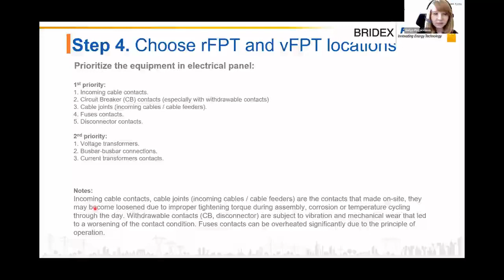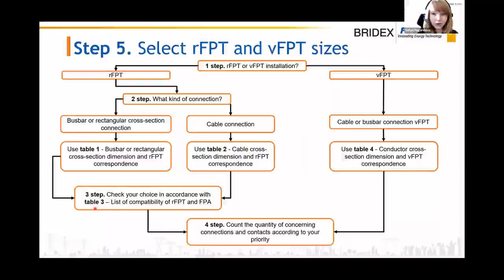This is a cross-section of middle voltage switchgear. So we install gas stickers on busbar connections, especially those made on site, on moving contacts of withdrawable contacts of circuit breakers, on contacts of current transformer, on incoming cable contacts, and on moving contacts of withdrawable voltage transformer. Next slide. Selection of gas sticker and visual sticker sizes. Gas sticker and visual sticker sizes can be installed either on bus bar or on cable connections. Next slide, please.